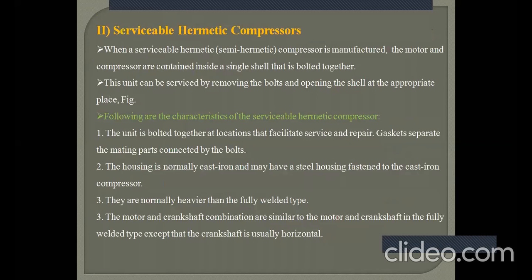Then the serviceable hermetic compressor. These compressors are quite widely used in the industry. As the name suggests, it is a serviceable hermetic compressor, known as a semi-hermetic. It is famous by the name semi-hermetic compressor, where the motor and compressor are contained inside a single shell that is bolted together. The compressor and motor are again in a single shell, but bolted together, and this unit can be serviced by removing bolts and opening the shell at the appropriate place.